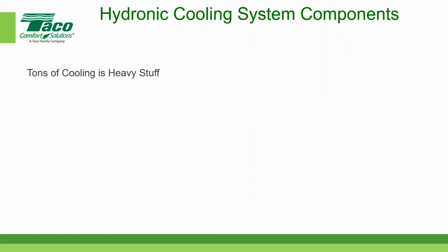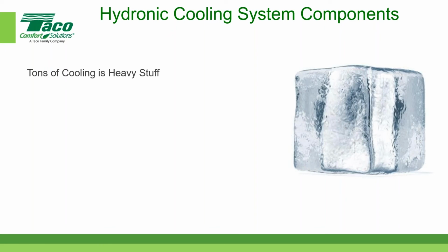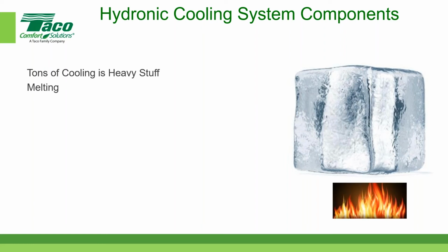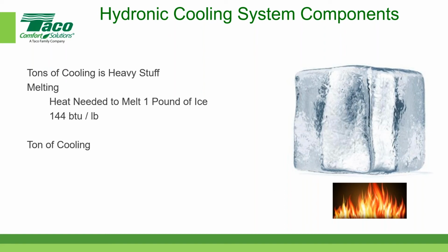Tons of cooling is, I like to say, heavy stuff. So where did the term ton of cooling come from? Well, it turns out that if we take a block of ice and add heat to melt the ice, the heat needed to melt 1 pound of ice happens to be, coincidentally, and this is a cool number when you think about it, 144 BTUs per pound. That's how many BTUs of heat you have to add to a pound of ice in order to melt it, or change it from a solid to a liquid. Well, the ton of cooling actually comes from the following. It's the amount of heat needed to melt 2,000 pounds of ice in 24 hours. And 2,000 pounds is another name for a ton of ice.